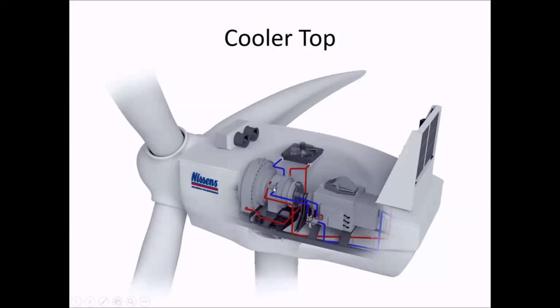Although they have internal air cooling, internal water cooling, or internal liquid cooling within their systems, some part of that heat will be transferred outside the gearbox or generator enclosures. So more heat gets generated in this particular room, and this nacelle is completely enclosed such that there won't be any airflow or water flow from outside.